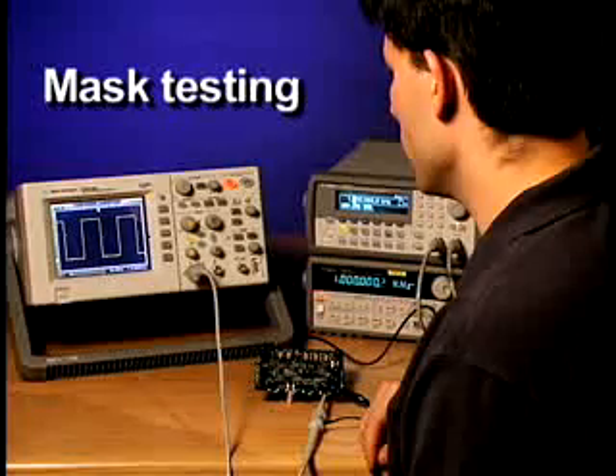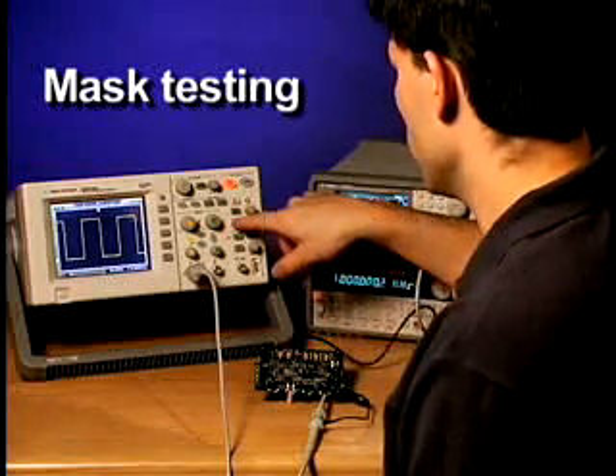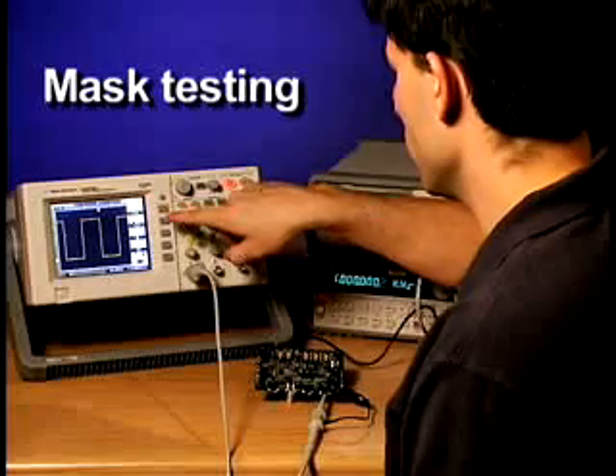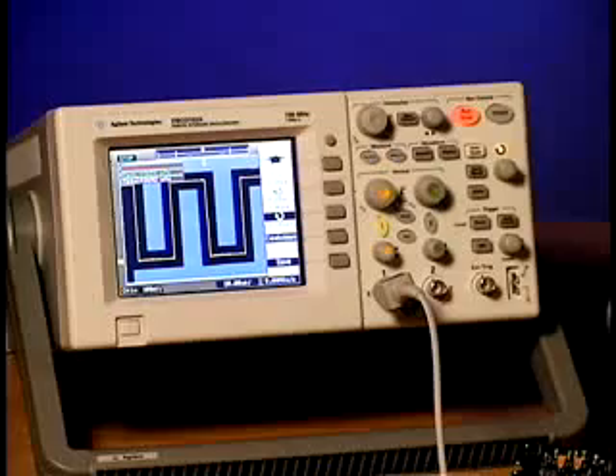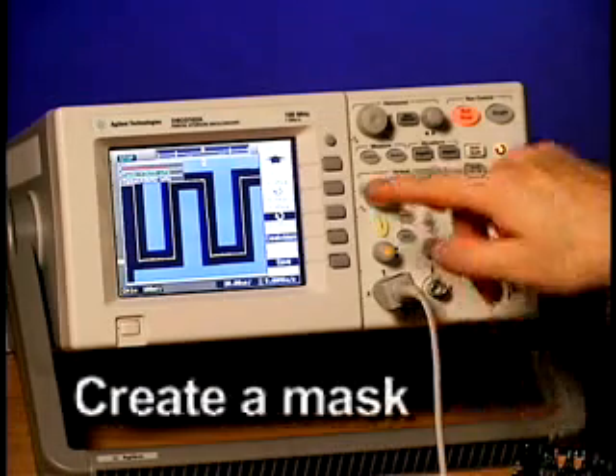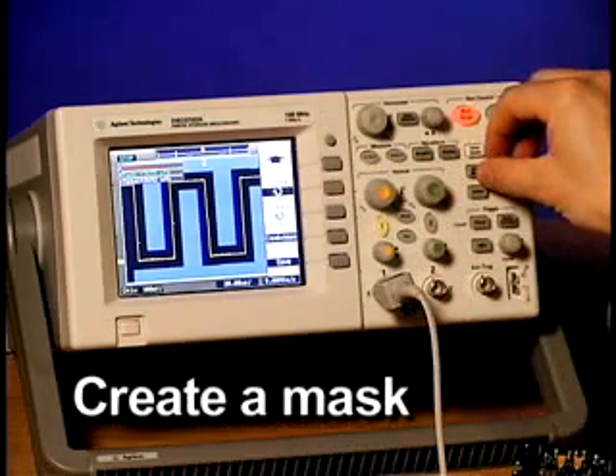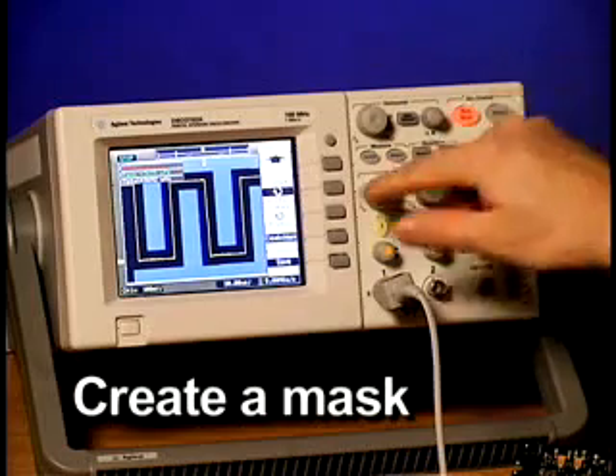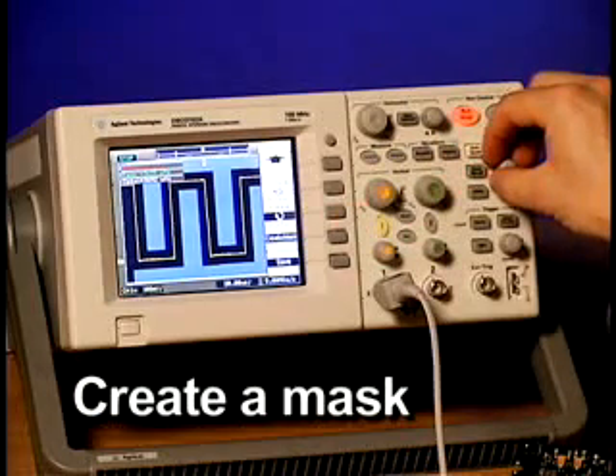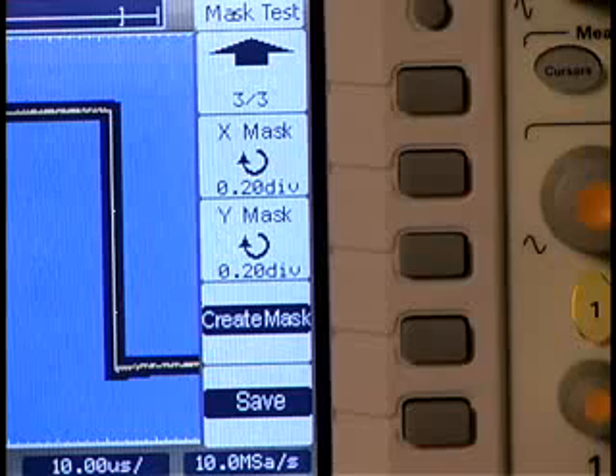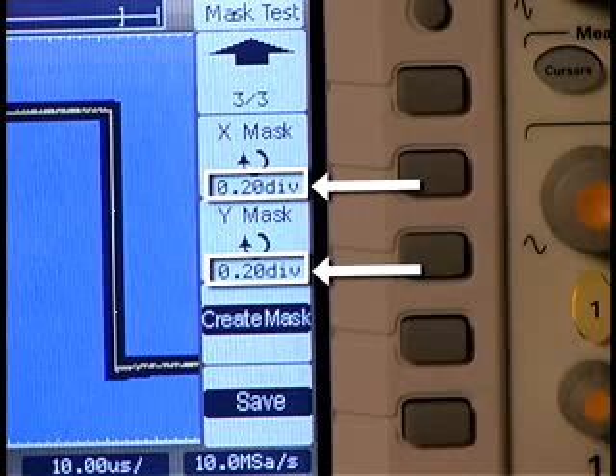A second and more sophisticated way to compare a reference waveform is using mask testing. This is a standard feature of the DSO 3000 and a valuable cost-effective tool for testing conformance to a reference waveform in production or R&D environments. For instance, here in creating a mask, we've set an allowable limit of signal variation in terms of vertical and horizontal divisions. In this particular case, we've set a threshold of 0.2 divisions.